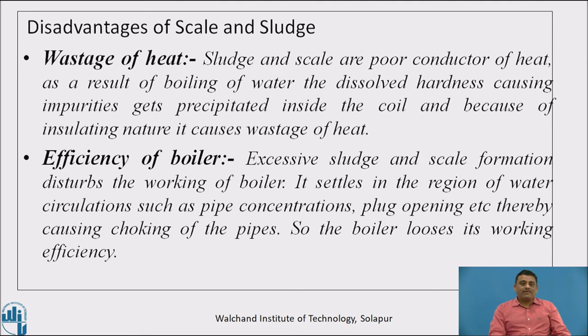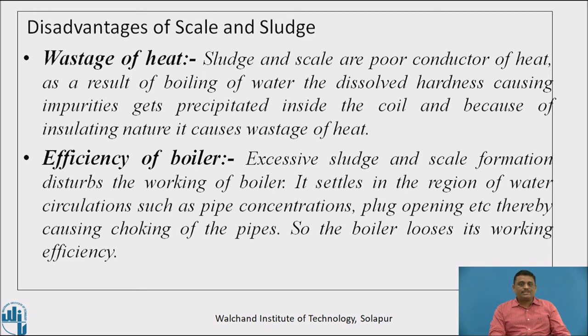Now we will see the disadvantages of scale and sludge. The first is wastage of heat — sludge and scale are poor conductors of heat. As a result of boiling, dissolved hardness-causing impurities precipitate inside the coil and, due to their insulating nature, cause wastage of heat. The second effect is reduced boiler efficiency — excessive sludge and scale disturb the working of the boiler by settling in regions of water circulation such as pipe connections and plug openings, causing choking of the pipes and loss of working efficiency.